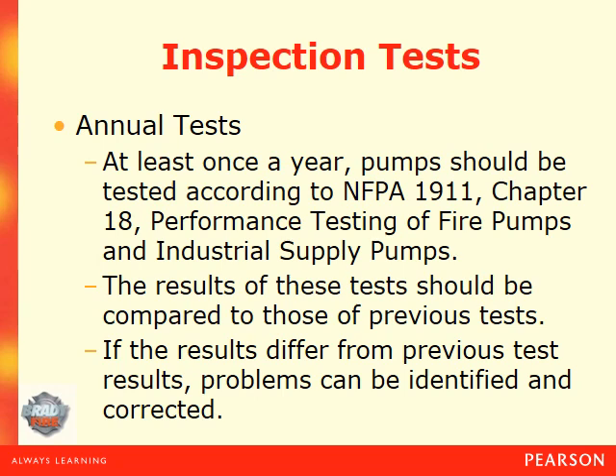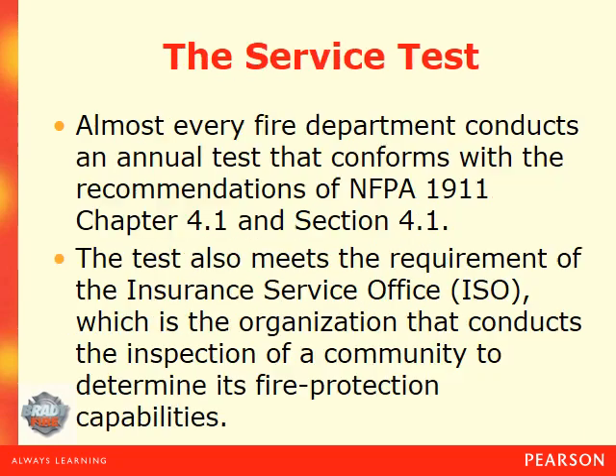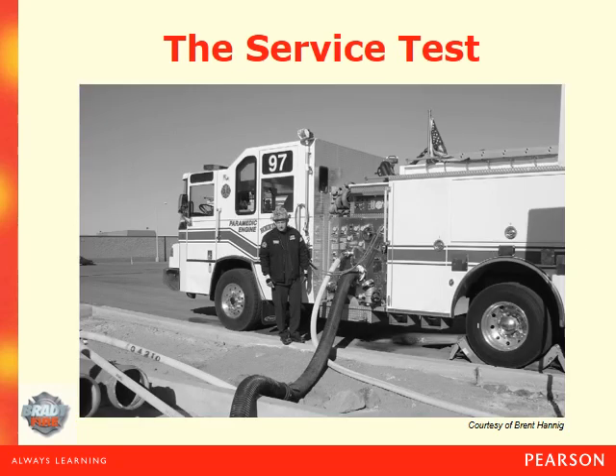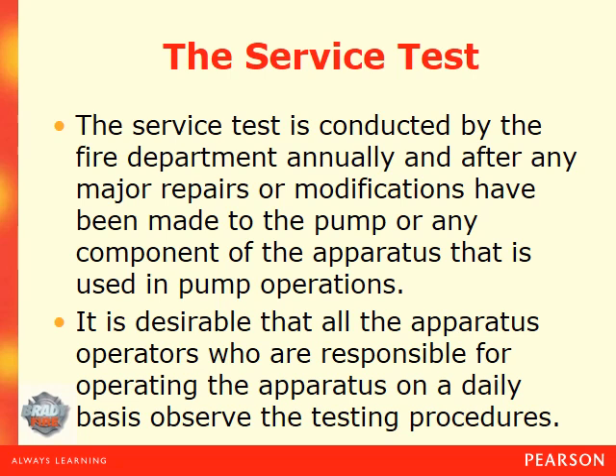Annual test: at least once a year, pumps should be tested according to NFPA 1911, Performance Testing of Fire Pumps and Industrial Supply Pumps. The results should be compared to those of previous tests — if results differ, problems can be identified and corrected. Almost every fire department conducts an annual test that conforms with NFPA 1911, which also meets the requirements of the Insurance Service Office (ISO), the organization that inspects communities to determine their fire protection capabilities. The service test is conducted annually and after any major repairs or modifications to the pump or apparatus used for pump operations.